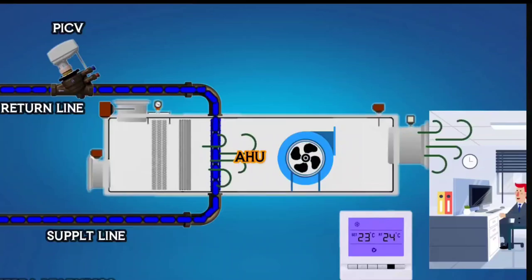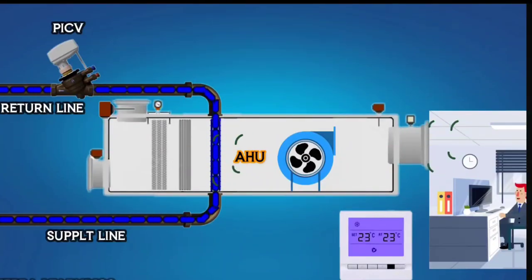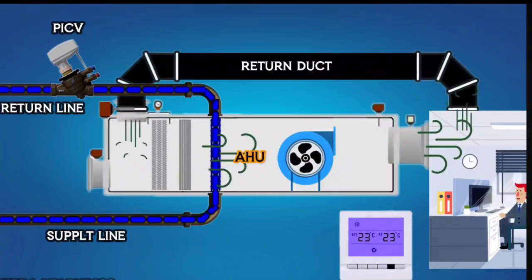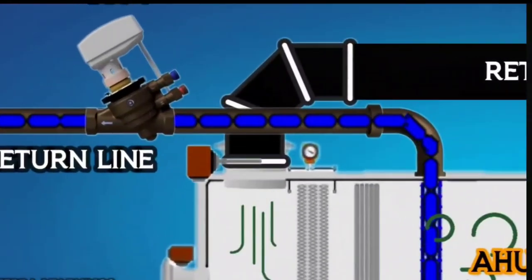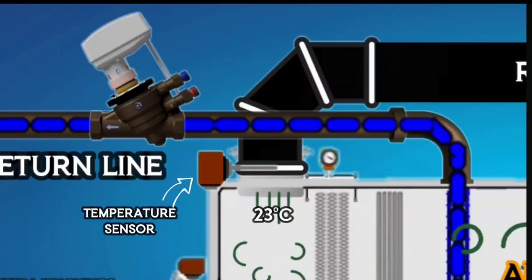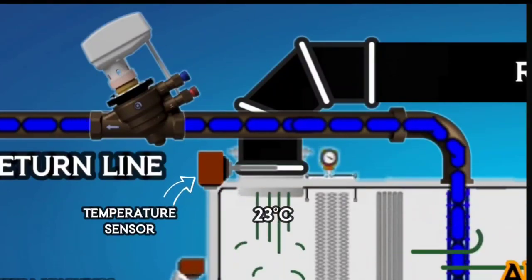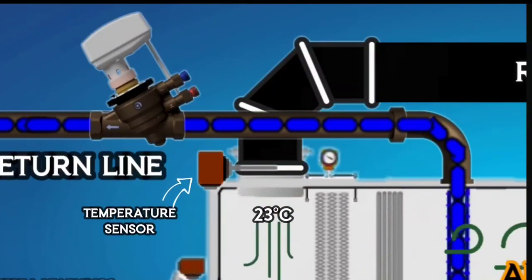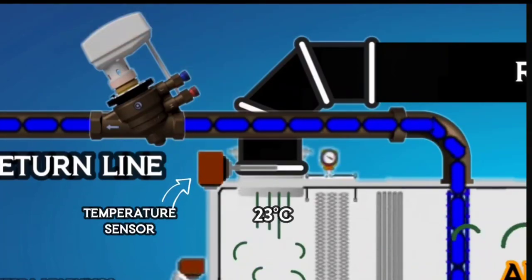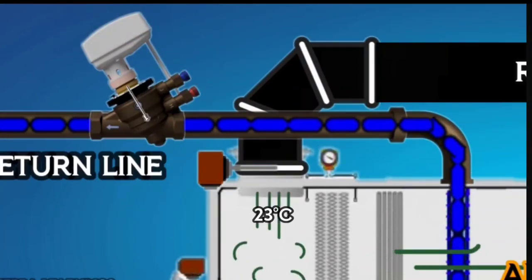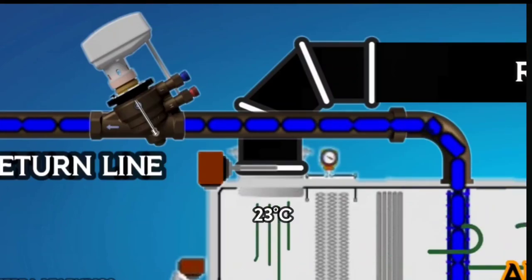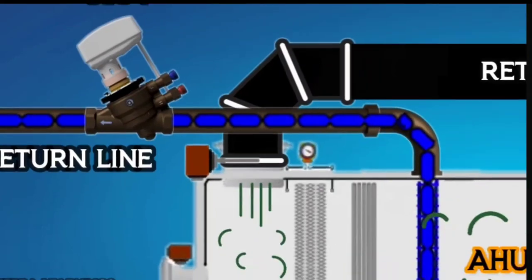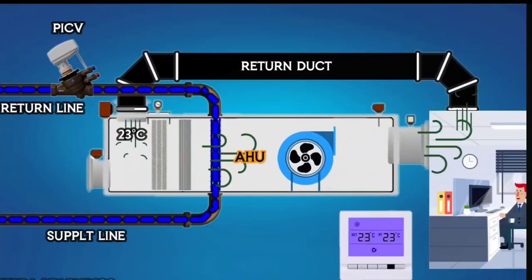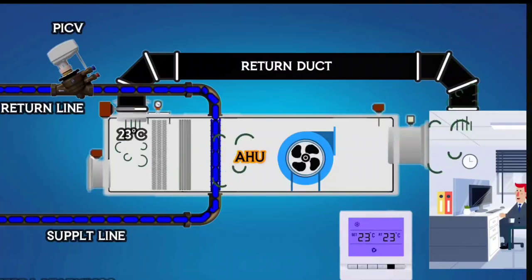Now, if the room reaches the set point temperature, then the room does not require cooling. So, what happens now? When the air enters the AHU through the return duct, the temperature sensor in the AHU senses the temperature of the return air. If the temperature reaches the set point, the sensor sends a command to the actuator. After the command goes to the actuator, it pushes down the stem and stops the water flowing into the pipeline. Then, the flow of chilled water inside the coil of AHU will stop. It prevents the cold air from entering the room.